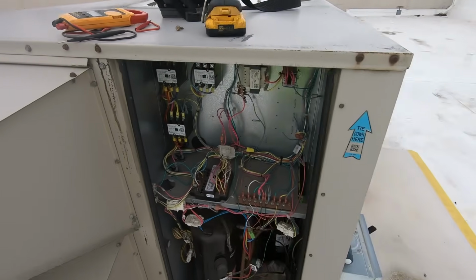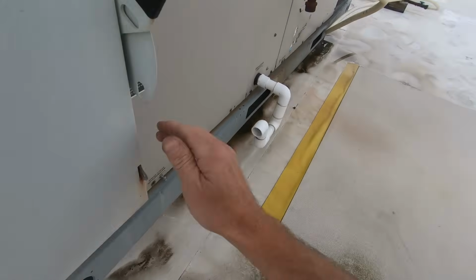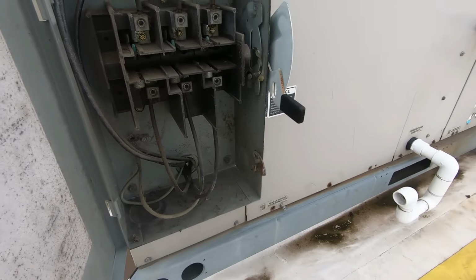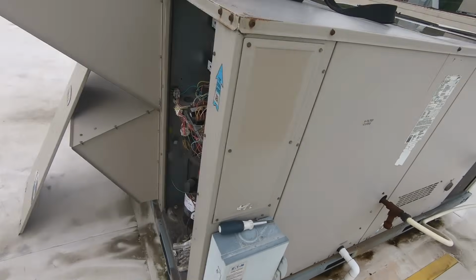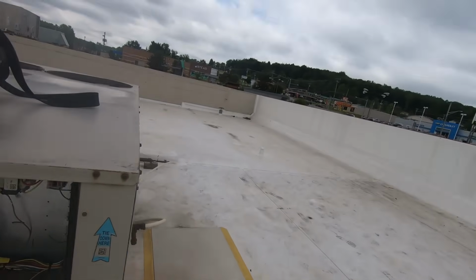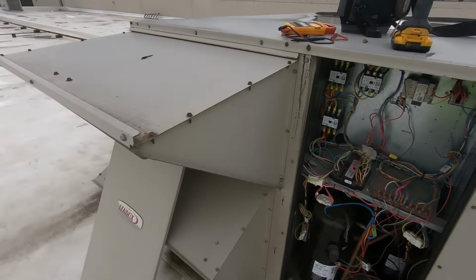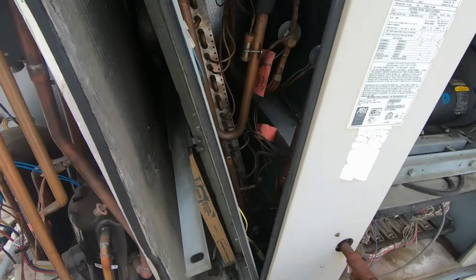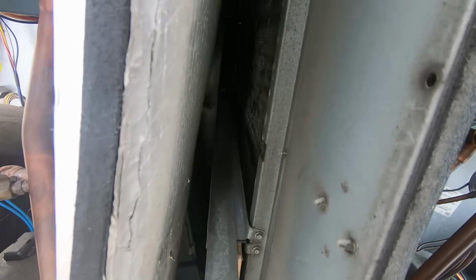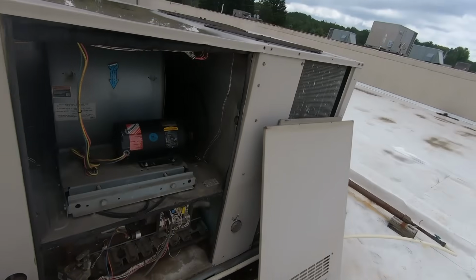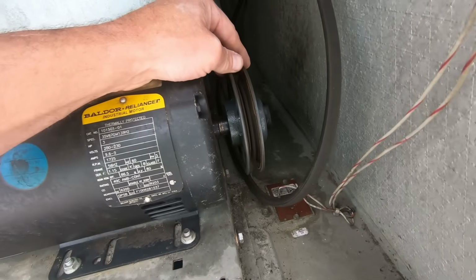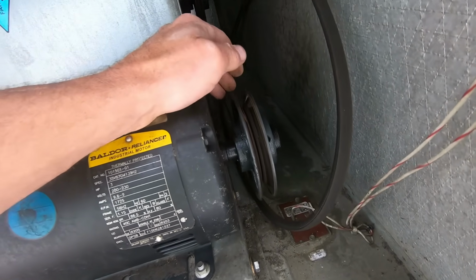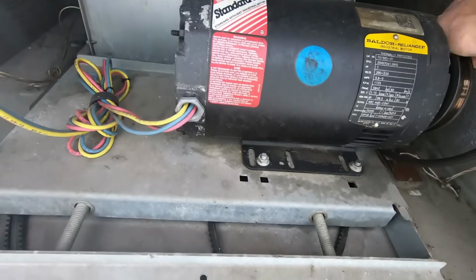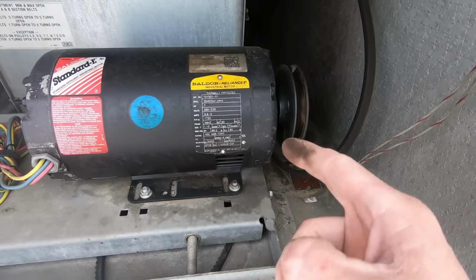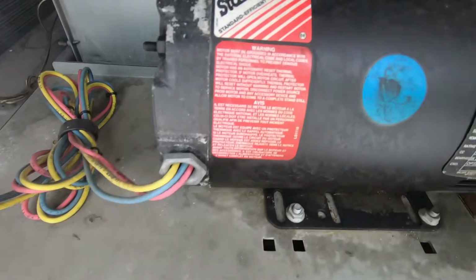Let's give it a quick look before we go find power. See if we have a breaker off. Let's pull this. No fuses, so it's off at the breaker panel. I'm gonna open it up, see if anything's shorted to ground right off the bat, and then we'll go try to find the breaker. Well, you can see the state of the filters. Coil's dirty. This guy's getting a full coil cleaning. The pulley on the motor is wound all the way in. The set screw must have come loose. It wound itself all the way in. Bearings are clicking. This guy's gonna get recommended a new motor and a new pulley. Bearings on the blower.